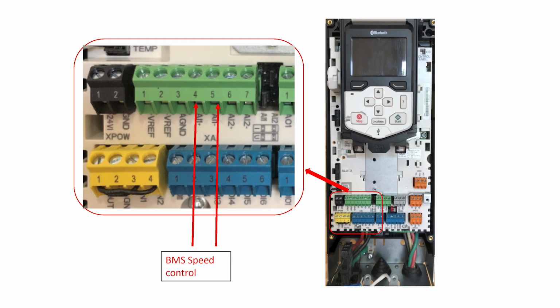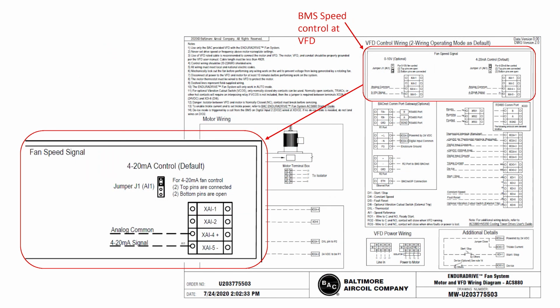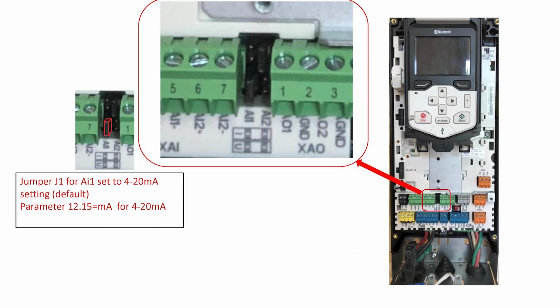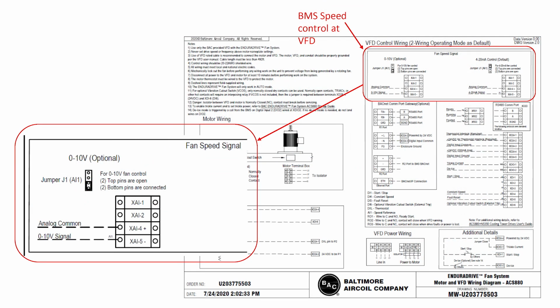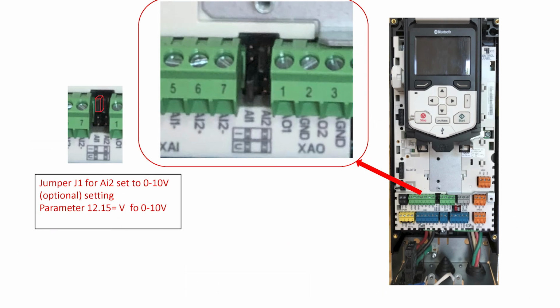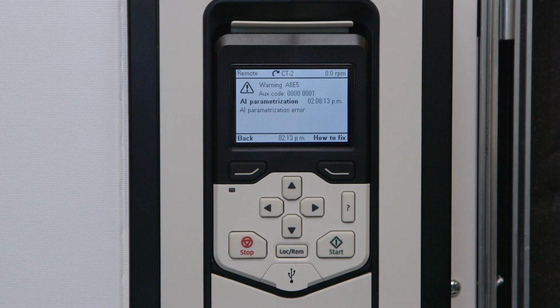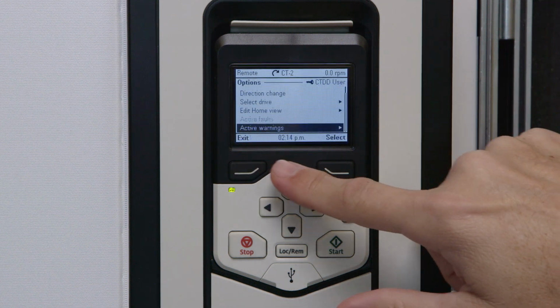Another common error occurs when the setting for analog input 1 is mismatched. Most of the time, analog input 1 is connected to the BMS speed signal. When jumper 1 is connected to the top two pins for a 4 to 20 milliamp speed, the parameter 12.15 will also need to be set to milliamps to avoid error. Conversely, for a 0 to 10 volt signal, jumper 1 is connected to the bottom two pins, and parameter 12.15 needs to be set to volts to avoid the error.